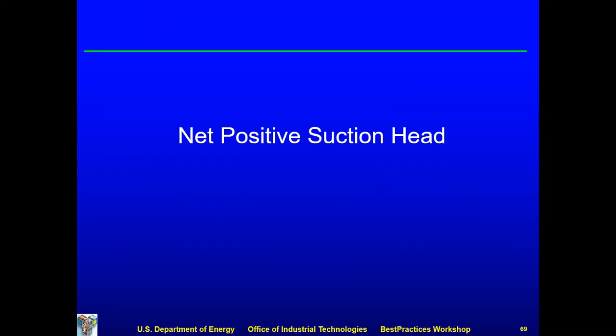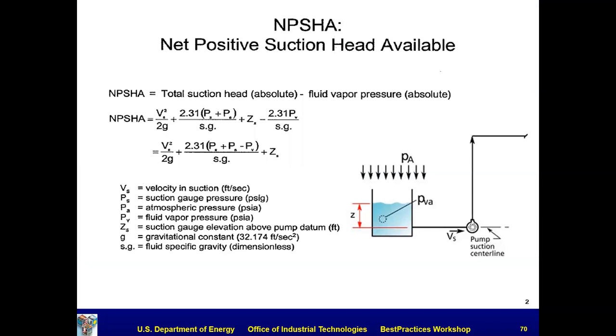Okay, net positive suction head. We've talked a little bit about that. Here are some equations where you can calculate it. It is the total suction head in absolute pressure minus the fluid vapor pressure. That is what you actually have. This would be a velocity term, V squared over 2g, at the suction of the pump. The 2.31 assumes standard water, and when I divide by specific gravity, this converts from PSI to feet of head. So this would be the suction pressure, this is the atmospheric pressure, the second term, and this is any elevation head that you have behind it. This is the vapor pressure. And so those terms are calculated in those equations.